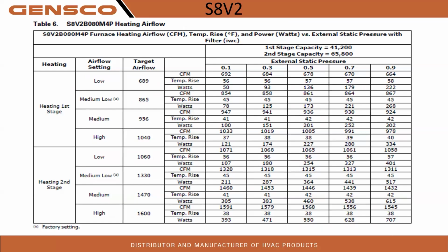S8V2. So here's the S8V2, 80% variable speed, 80,000 4-ton. We're going to have a 2-stage. So our default is medium low. So target airflow is 865. So at 0.5 static, with the temp rise of 45, so we're going off of there. We can be at medium low. We're actually 861. 864 is most common with the 0.7.